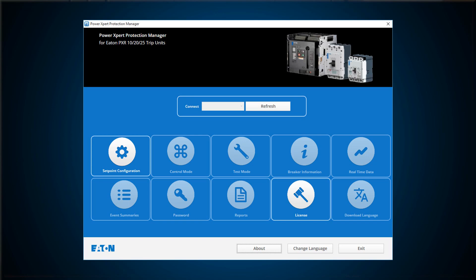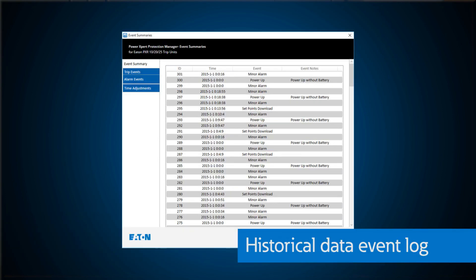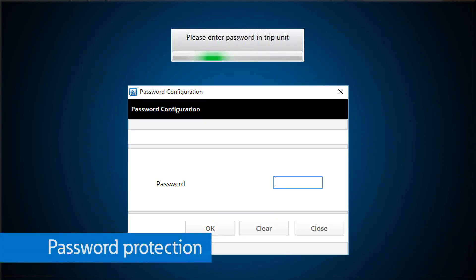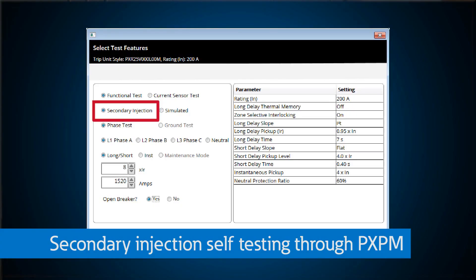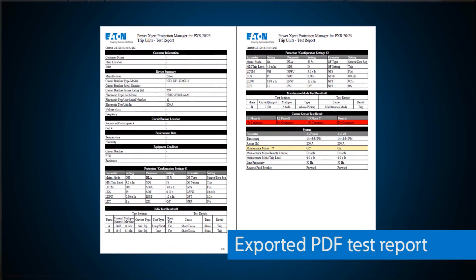PXPM is your one-stop shop to get all kinds of information out of the breaker. You can upload and download protection settings and see the resulting time-current curves. You can access historical data through a comprehensive event log. You can pull live metering data, and you can capture waveform data before and after a fault event. Everything is secure and password protected, and now it even offers a new form of testing. In the past, our legacy products used a separate test kit to test the protection routines and trip actuator on the breaker. Now, with PXPM, you can actually do a secondary injection test with just your laptop, sending a signal into the breaker CTs to simulate an actual fault, and the breaker will respond just as it would if the fault was real. After the test, PXPM even provides a clean PDF test report detailing any changes in settings, what protection settings trigger the trip, how fast the breaker reacted to the fault, and it even has room for customization to include customer and assembly information.